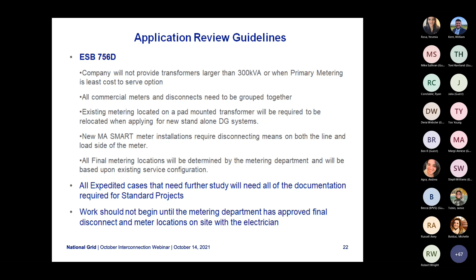So the screening process is always required for expedited and standard projects. Expedited projects require screening review to be completed within 25 business days. Standard projects require an initial review to be completed within 20 days. Some of the things that we check during screenings on a project: if it's a radial or network system, if the equipment is UL 1741 SA listed, if the proposed service configuration will work for the project, does the proposed DG system pass substation backfeed and islanding screenings? If any of those checkpoints fail, we typically require additional study before providing an ISA.